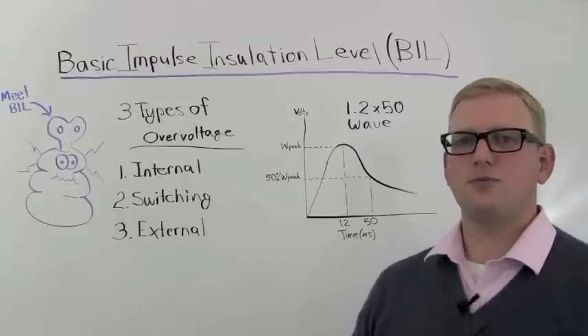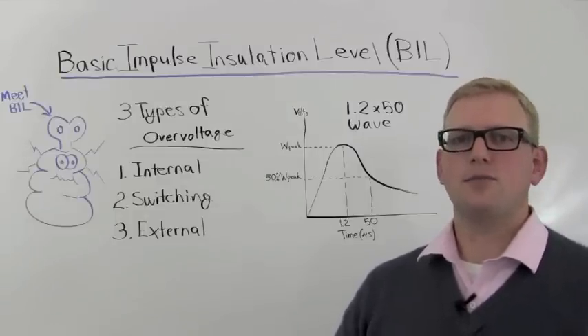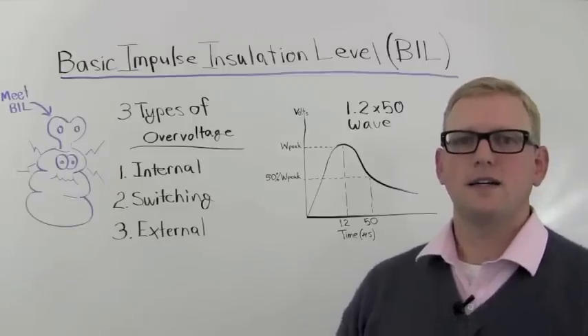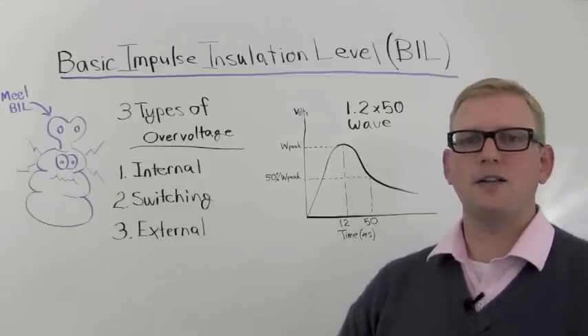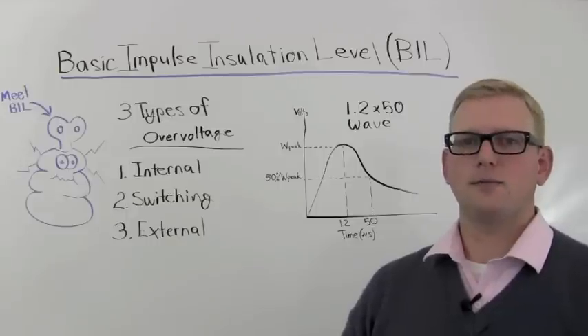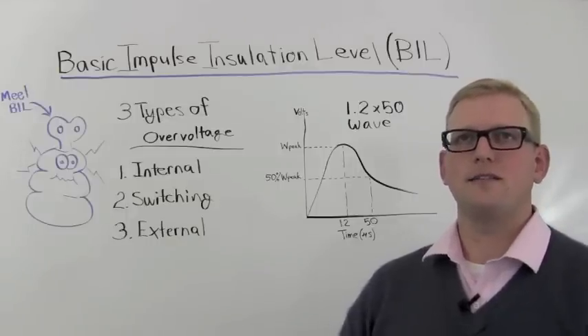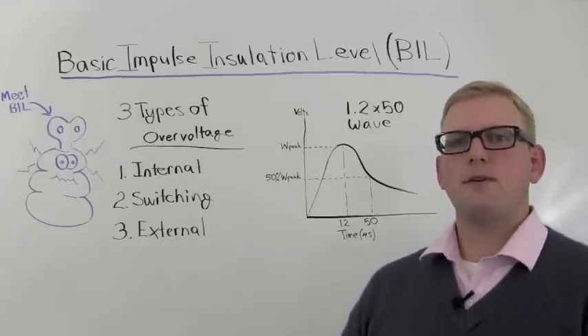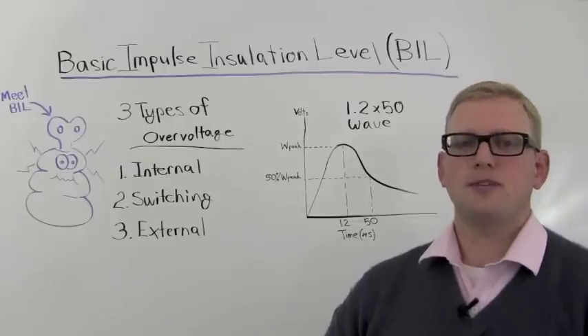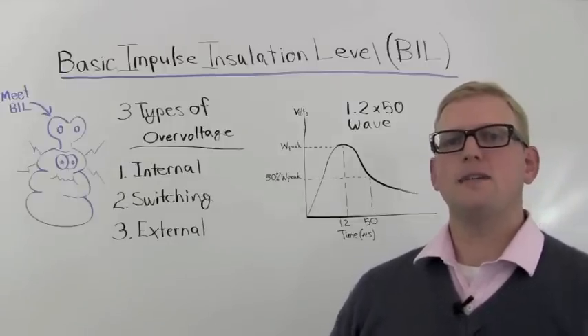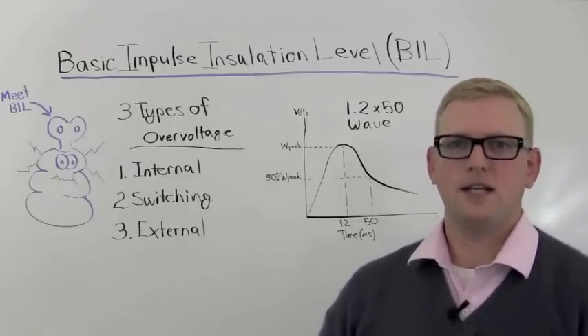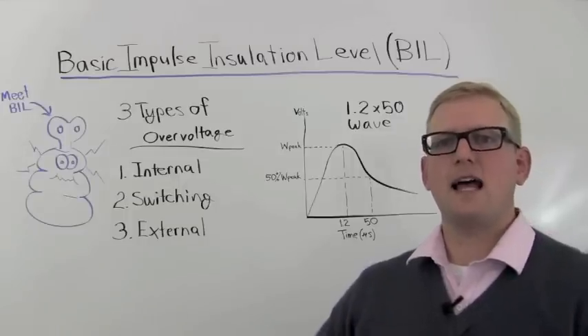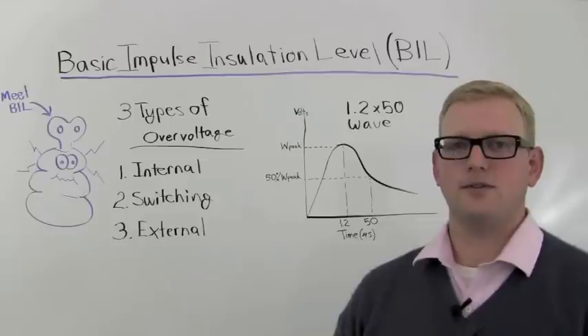Manufacturers will test their equipment and provide levels that are adequate for that voltage rating. For example, a 34.5 kilovolt rated transformer — that's the high voltage side of a typical medium voltage transformer — will have a BIL, or Basic Impulse Insulation Level rating, of 150 kilovolts. That piece of equipment will withstand a peak surge up to 150 kilovolts.